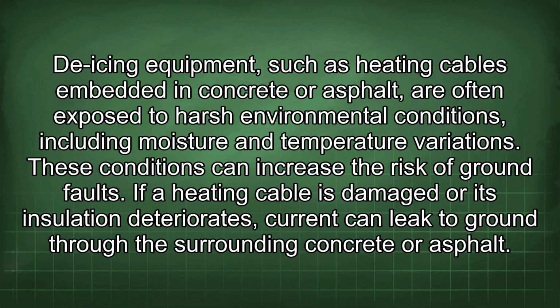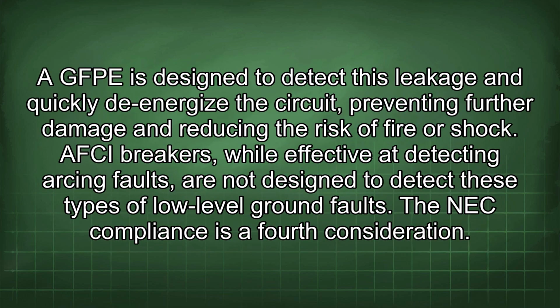If a heating cable is damaged or its insulation deteriorates, current can leak to ground through the surrounding concrete or asphalt. A GFPE is designed to detect this leakage and quickly de-energize the circuit, preventing further damage and reducing the risk of fire or shock. AFCI breakers, while effective at detecting arcing faults, are not designed to detect these types of low-level ground faults.